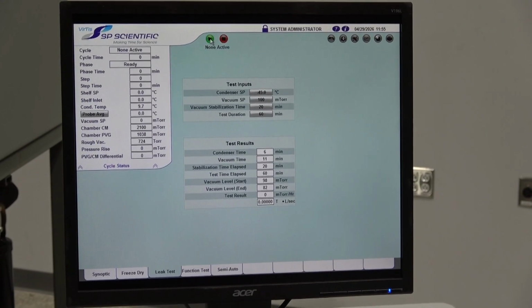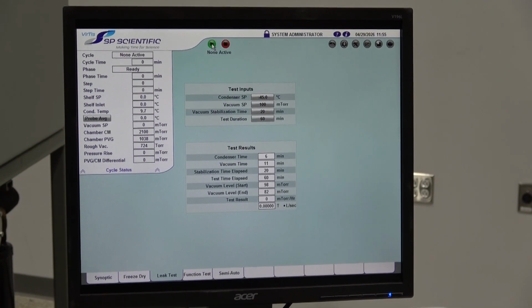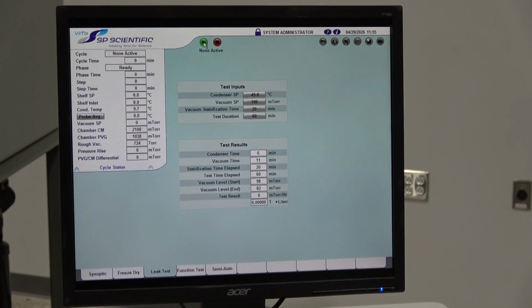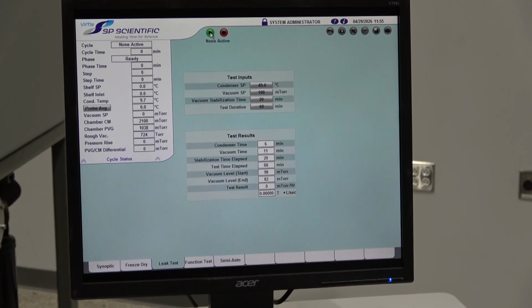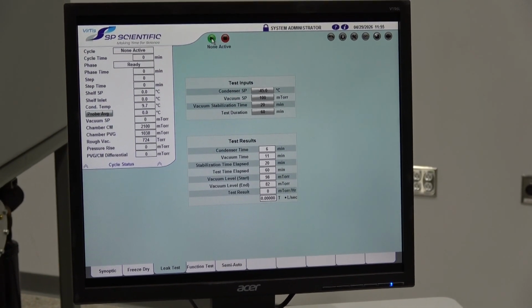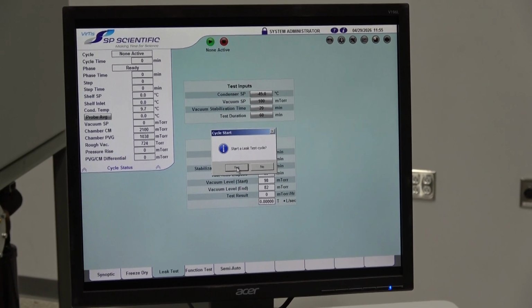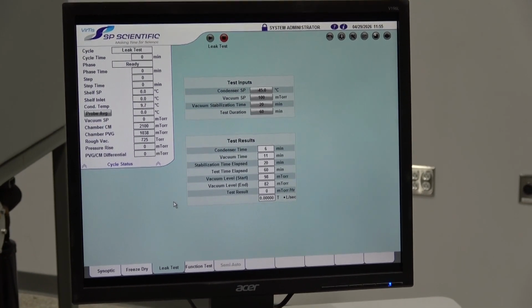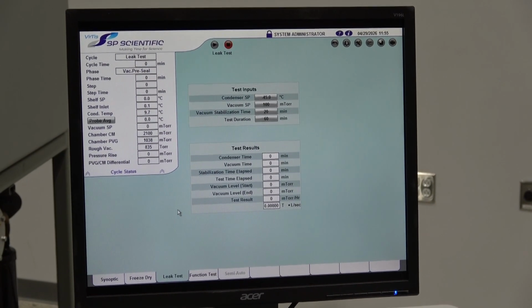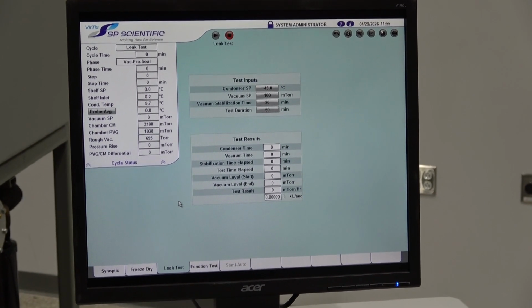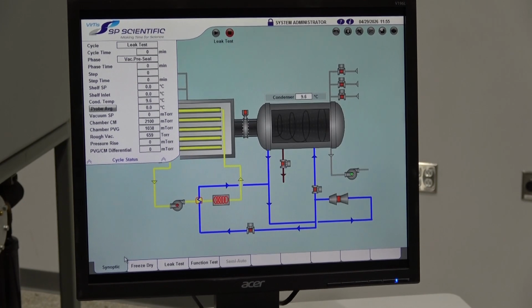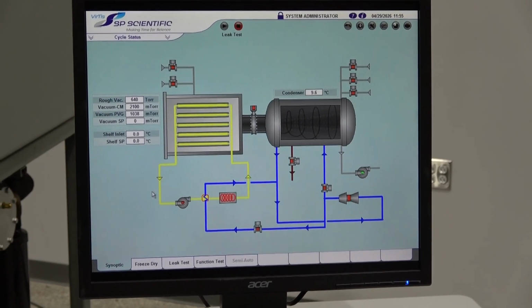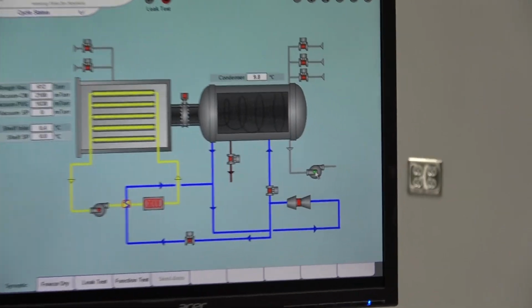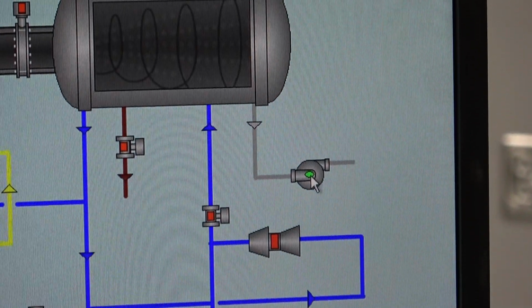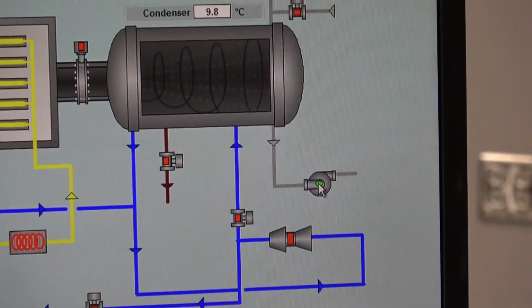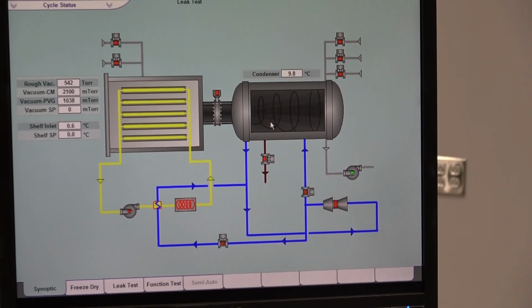And as soon as we hit this, it's going to start running that leak test, and essentially it's going to get the condenser cold and then run the vacuum pump. So you'll be able to hear the compressor running on this also. So we're going to say yes, start the leak test. So we had the isolation valve, and we can move over to the synoptic view here. And you can see right here that this is green now. That means that the condenser is running. Or I'm sorry, the vacuum pump is actually doing a pre-seal right now.